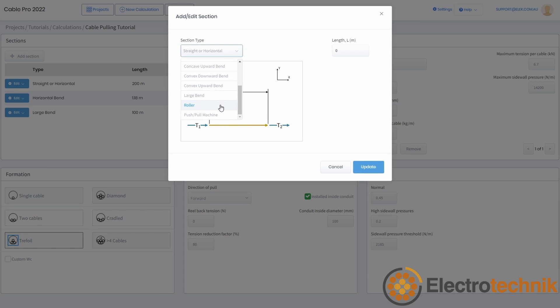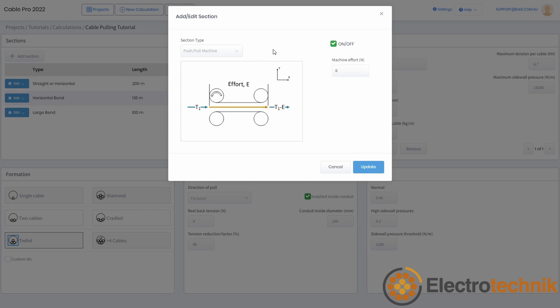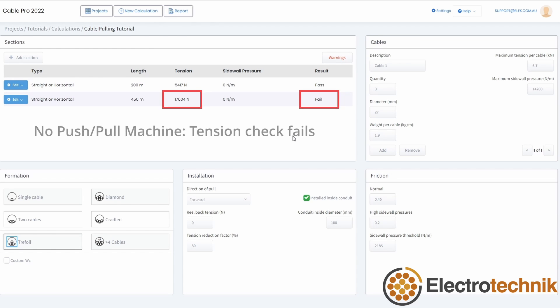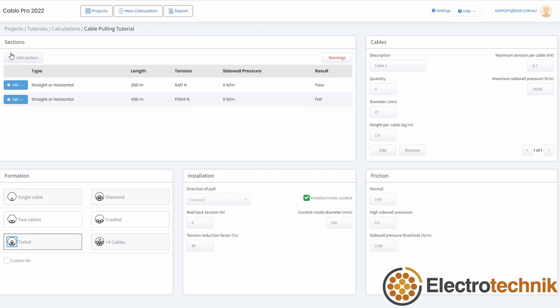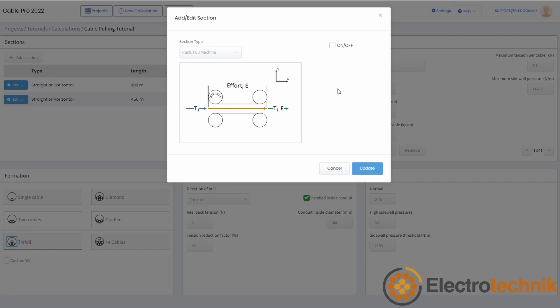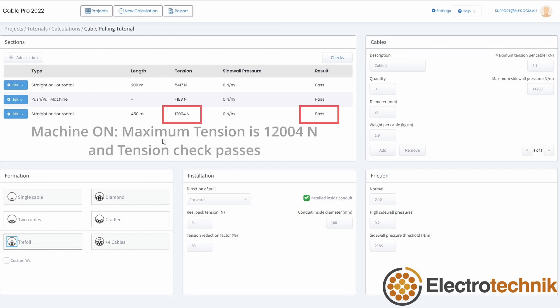There are rollers and push and pull machines which can be inserted at any point along your cable pull as required to assist with the installation of the cables. Push and pull machines are useful for when maximum pulling tension is exceeded. You can insert them into your cable pull to reduce the tension by the machine effort value, and you can experiment by keeping a machine at some intermediary point along your pull and switching the machine on or off to see its effects on the tension.